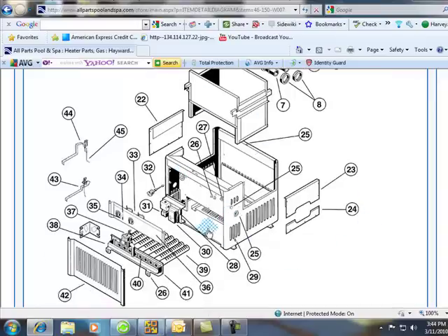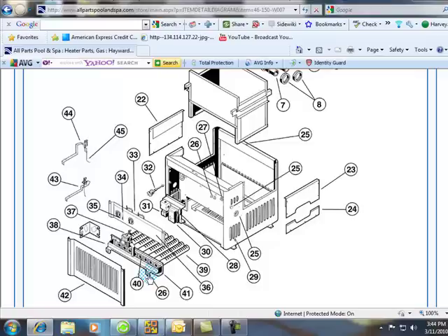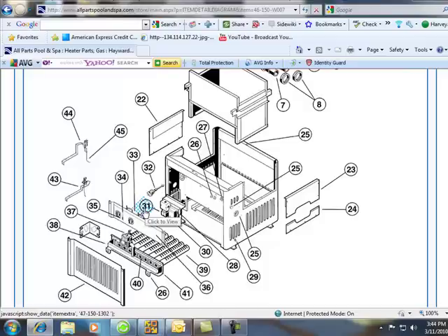You're starting to push back heat. Well, if you start pushing back heat, that sensor usually will go. So that's another thing you want to look for is this sensor. You never want to bypass any safeties. Seeing it out in the field. I don't have one, Harvey. I bypassed it. The thing went on fire. And I saw one burn half of the house down. Because somebody bypassed the safety.